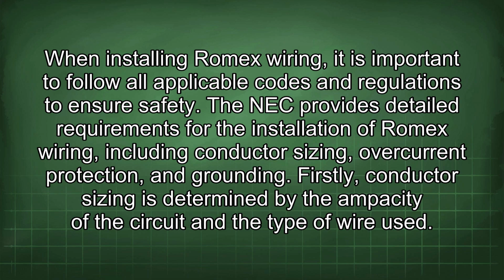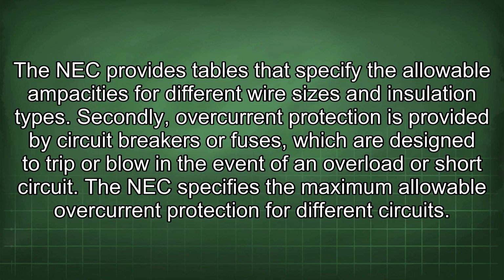Firstly, conductor sizing is determined by the ampacity of the circuit and the type of wire used. The NEC provides tables that specify the allowable ampacities for different wire sizes and insulation types. Secondly, overcurrent protection is provided by circuit breakers or fuses, which are designed to trip or blow in the event of an overload or short circuit. The NEC specifies the maximum allowable overcurrent protection for different circuits.